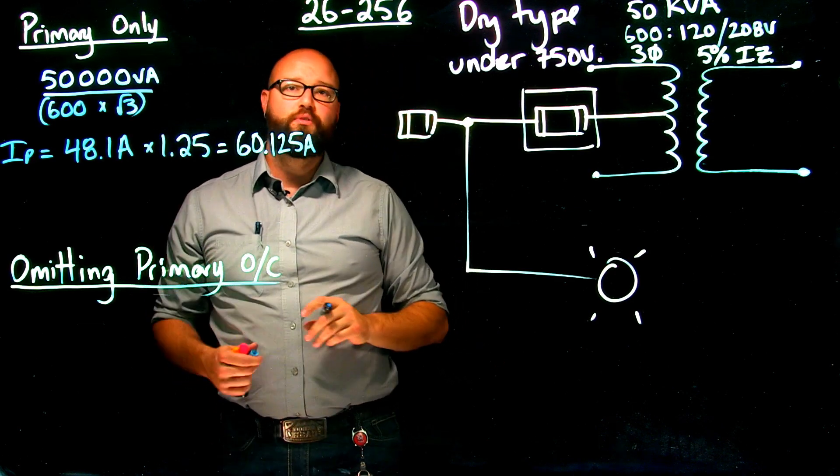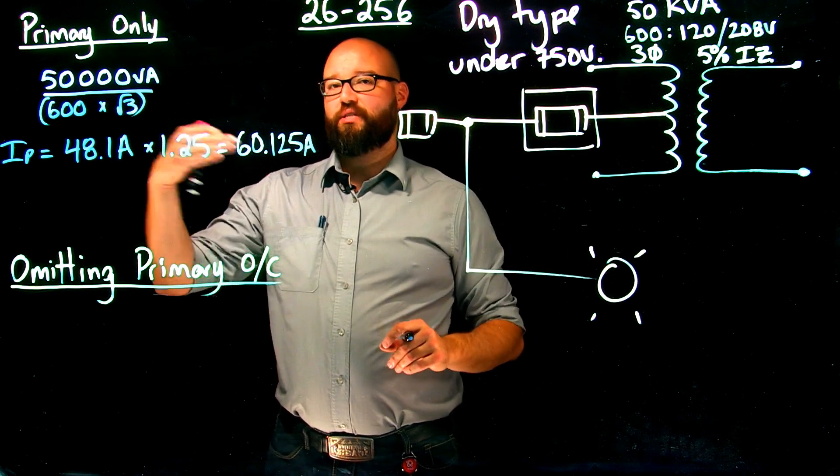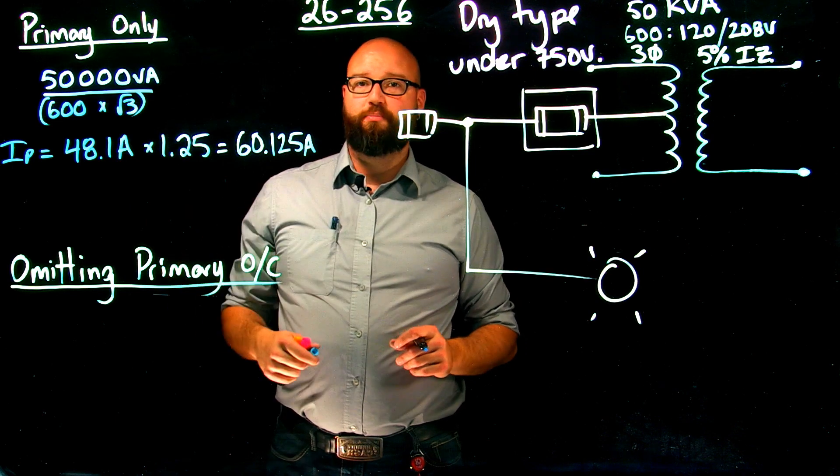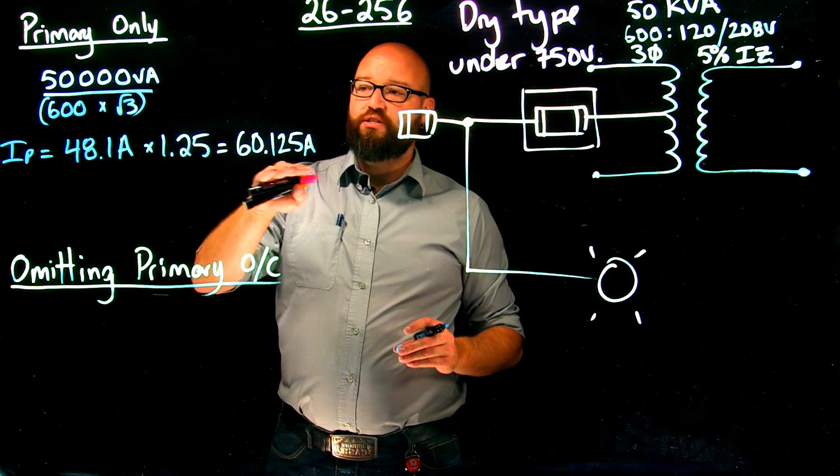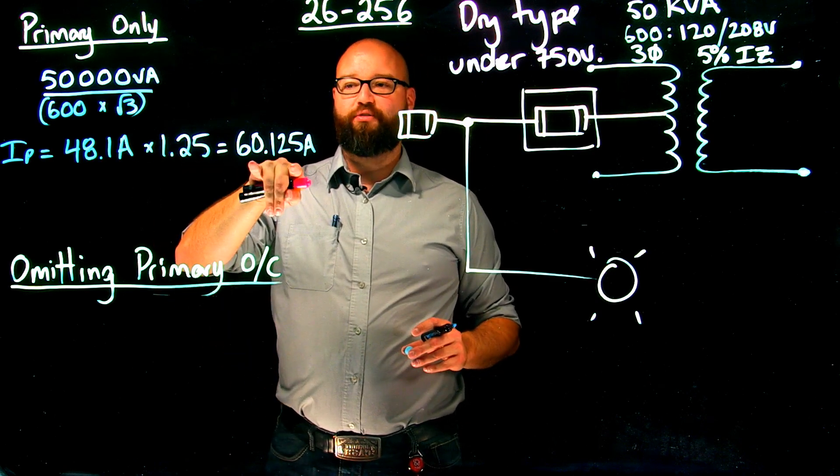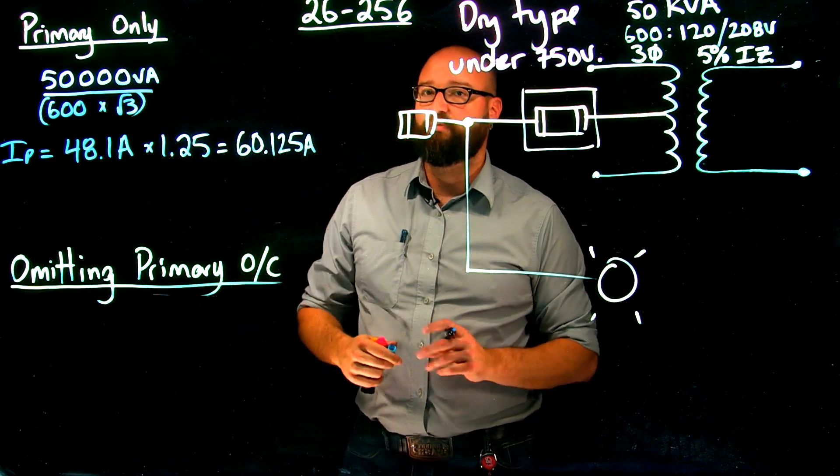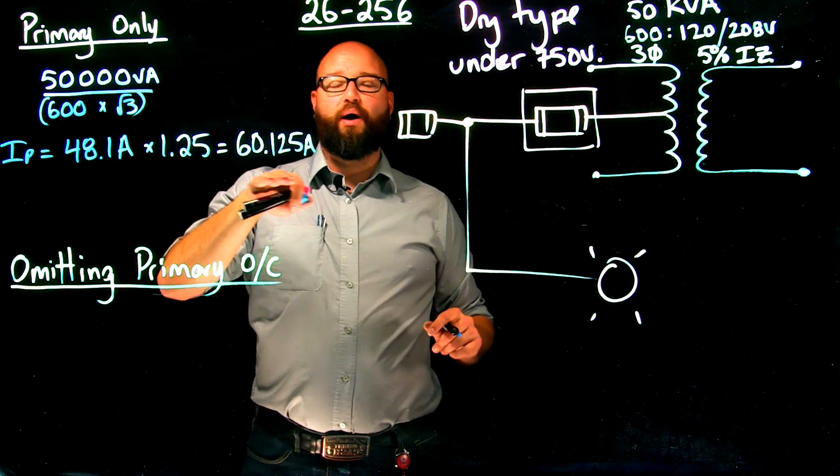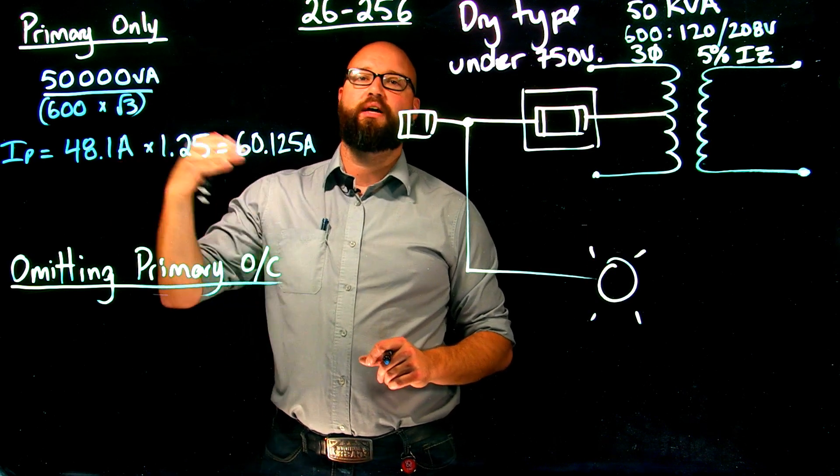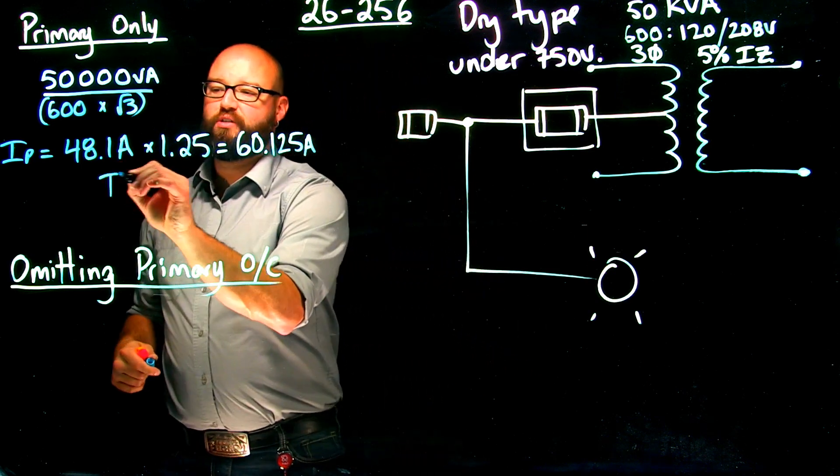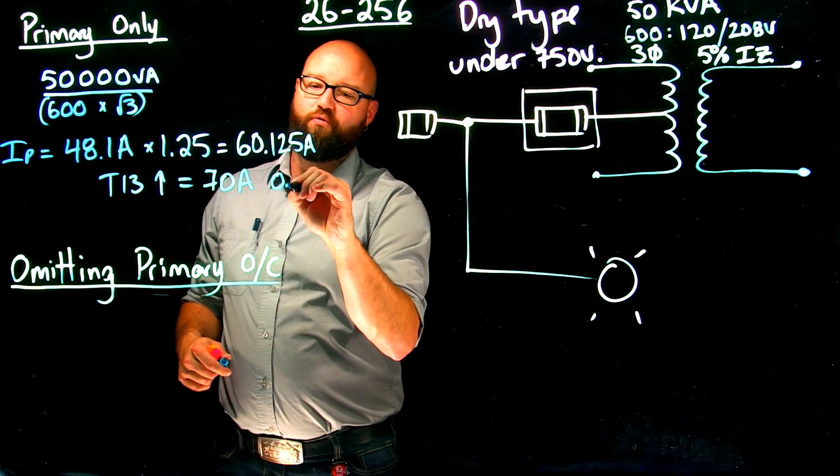Now subrule two deals with what happens when we omit that primary protection. We have to skip ahead to subrule three. This little part is buried in subrule three. It actually tells me in subrule one, if there is no overcurrent setting from table 13 at this right here, we are allowed to go up to the next available size. So it's a little bit buried in the actual rule, we have to read a little bit. But if there is no overcurrent rated at 125% of rated primary, we are allowed to go up to the next available size.